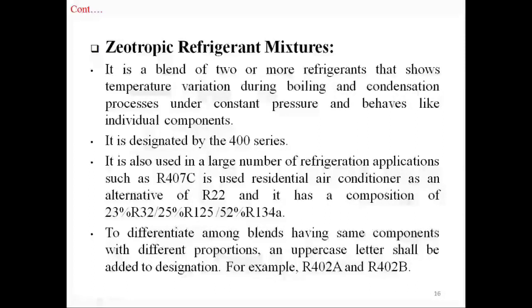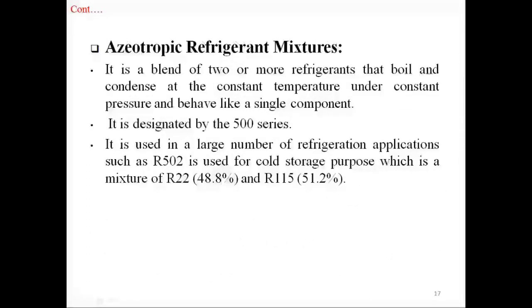R402A and R402B contain the same components but in different proportions. Next is azeotropic refrigerant mixtures. It is a blend of two or more refrigerants that boil and condense at a constant temperature under constant pressure and behave like a single component, whereas zeotropic refrigerants behave like individual components. It is designated by the 500 series. For example, R502 is used for cold storage purposes and is a mixture of R22 and R115.